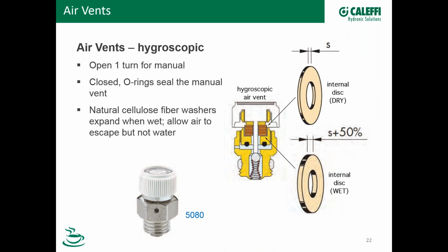Okay, hygroscopic. Now this is a really cool product. It's an air vent that is manual, but it's also automatic. Let's talk about that a little bit. What it has inside are these natural cellulose fiber washers that will expand when they get wet. So if you look at this cutaway, if you unscrew this top, you can actually open this inside here to do a manual vent, but normally you keep these closed. And when this is screwed closed, those O-rings form a seal right here. So this air is allowed to escape up through these fibers and then out the vent underneath the cap up here.